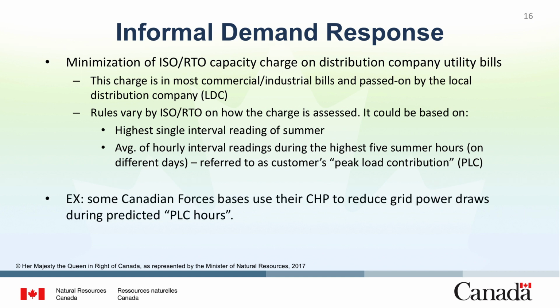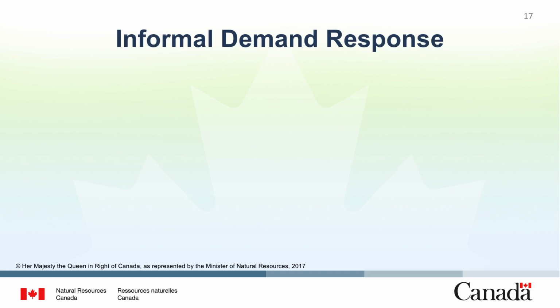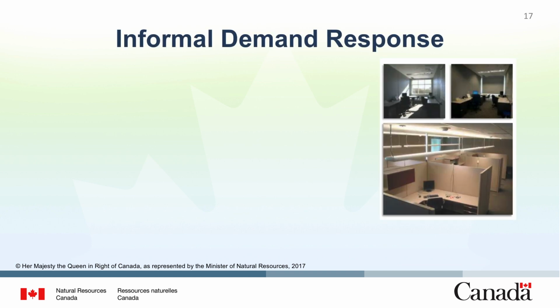For example, some Canadian Forces bases use their cogen or CHP to reduce grid power draws during predicted PLC hours. So how can we reduce demand during peak hours? In commercial buildings, HVAC and lighting energy use can be curtailed in response to a demand response event or to avoid peak demand charges. Buildings are usually designed and operated to deliver optimal comfort conditions for occupants. In its simple form, curtailment may only be temporary and only last for a few hours, but during those few hours, conditions may move outside traditional comfort zones.